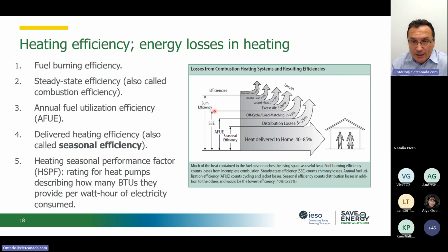Unfortunately, in our operation, in our buildings, we can't operate the boiler at steady state. We have on-off cycles, which add additional losses to our process. And again, in addition to that, we have the distribution system. What we actually use in the end, we define as seasonal efficiency. And this, as you see in this chart here, could be as low as 40%.